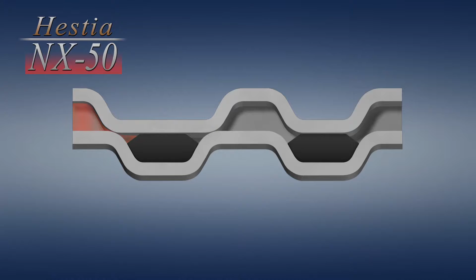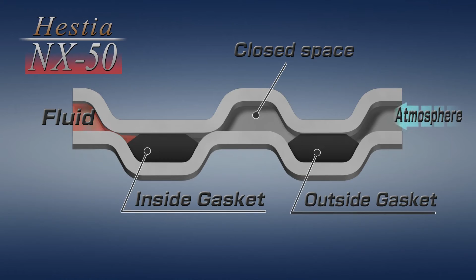A key feature of the Hestia NX-50 double-gasketed design is the manner in which the outer gasket protects the inner gasket from atmospheric oxygen, extending its life. The plate structure and groove design ensure the gaskets are completely confined by adjacent plates and remain stable against design basis fluid pressure. These factors contribute to the Hestia NX-50 reliability. A failure of the inner gasket does not lead to a breach of the pressure boundary, since both inner and outer gaskets must fail to lose component pressure integrity.